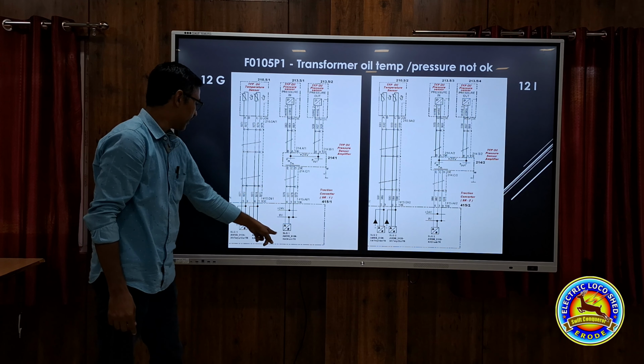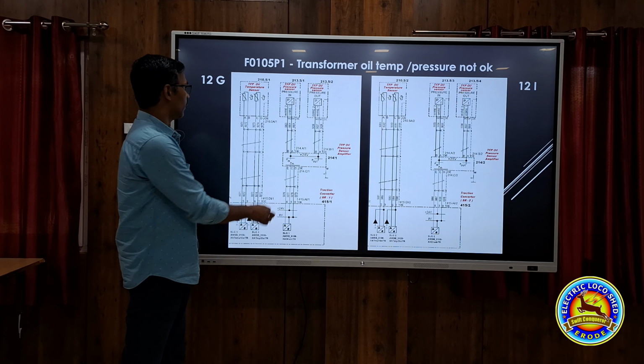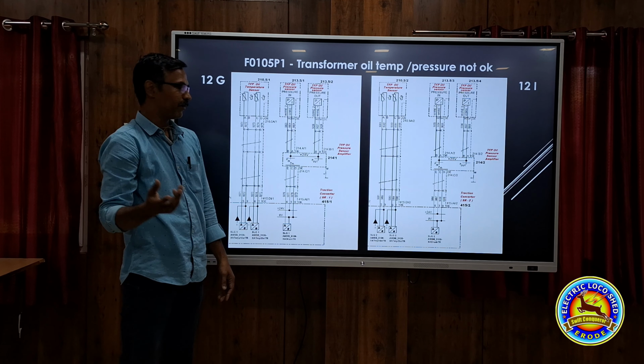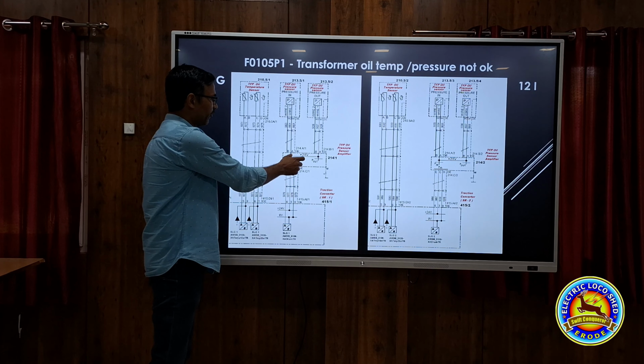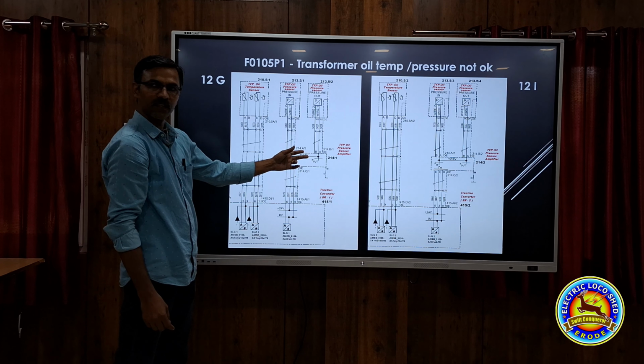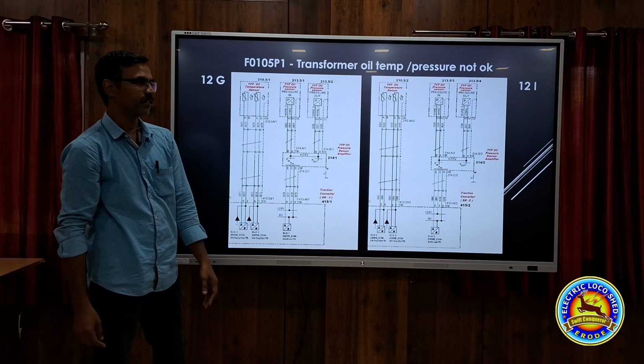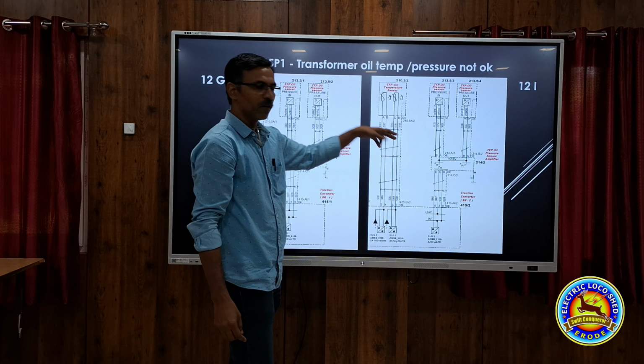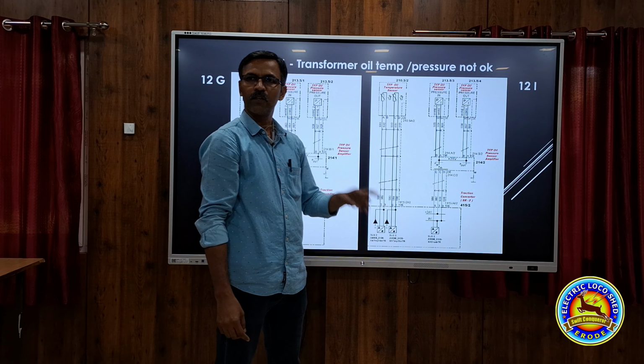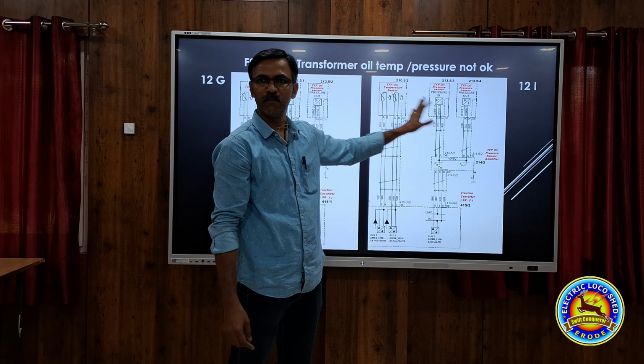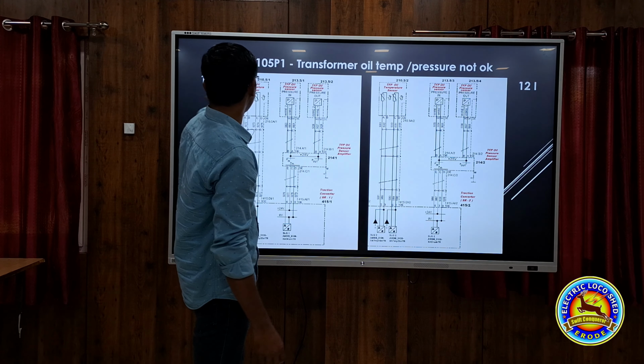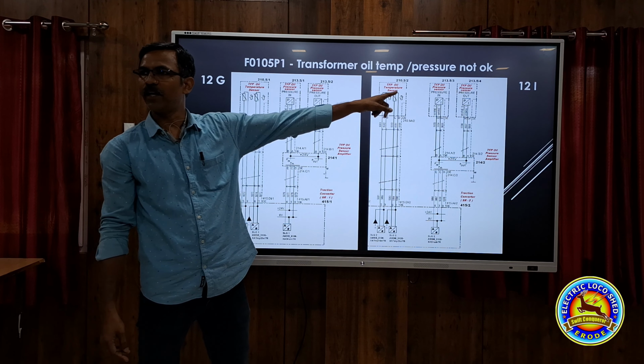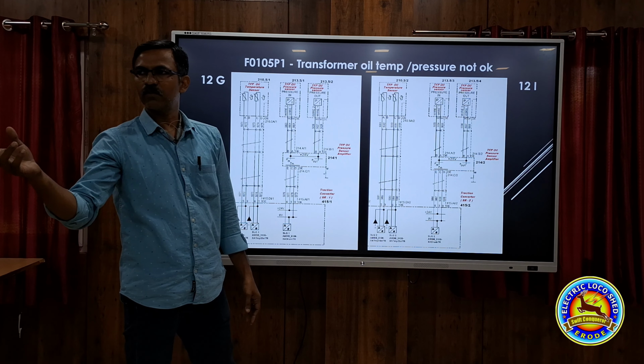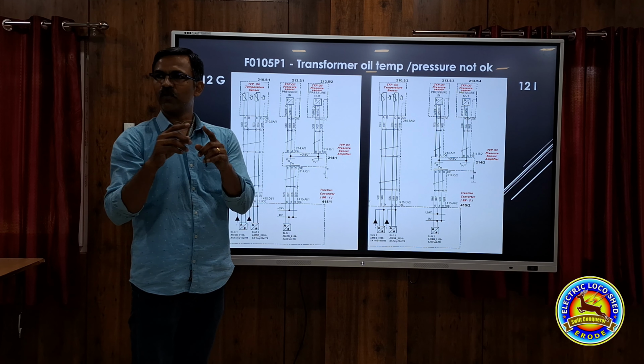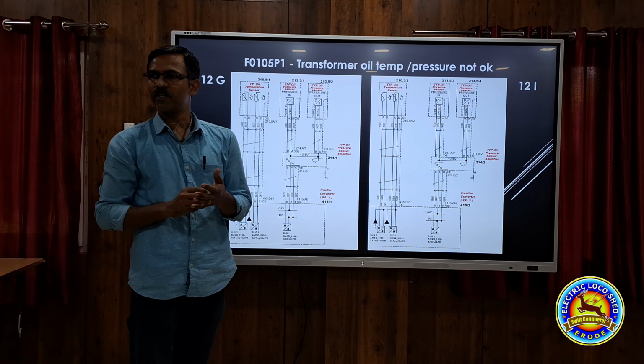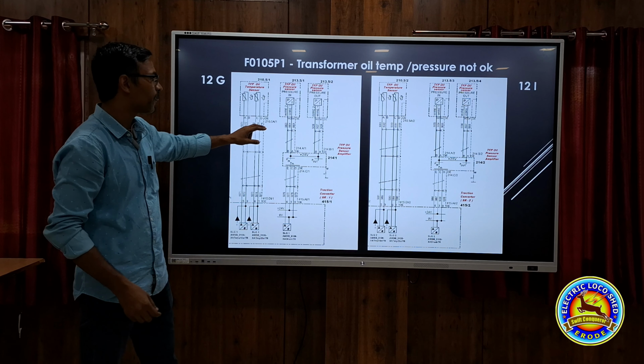So these are the signals. This pressure sensor should be fed with a 24 volt power supply. So that supply will go from this SR to the differential amplifier, and the differential amplifier will relay this 24 volt supply to both pressure sensors. The second page is exactly the same. The only thing is that it is going to SLG2, that is SR2. So this is the SR1 side, this is the SR2 side. Transformer 1 side, that is transformer 2 side. You can get these pages in 12G and 12I. I hope you understand 12G and 12I. If you go to the three-phase loco circuit, there will be a page number for each and every page. This comes at 12G.